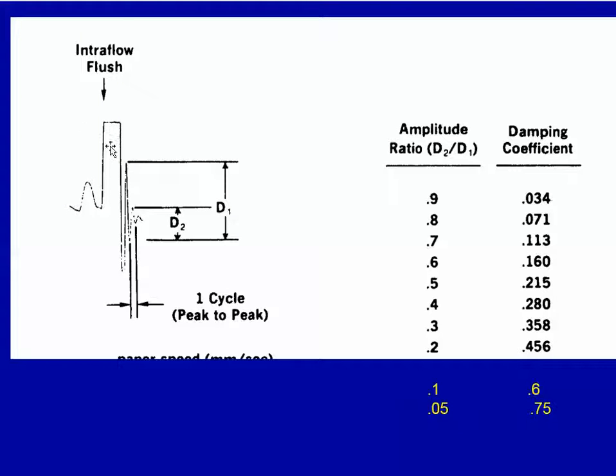Here is an illustration of the tracing. We have pulled the flush device and then let it go, producing a bouncing trace. From the interval between these cycles you can calculate the frequency, and from the reduction in amplitude from spike to spike you can determine the damping coefficient — taking the ratio of the second spike to the first spike gives you the damping coefficient.